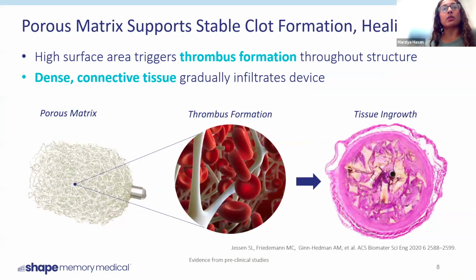And the way the embolization aspect of this device works is we have an extremely porous material where blood will make its way through the foam component, and it'll end up stagnating within the pores of the foam. That stagnation triggers the clotting cascade. And that's where we end up seeing the clot that forms to block the blood flow in the rest of the vasculature. And over time, what we have observed is that there is this dense connective tissue that eventually forms around the device. And I'll again go more into detail about this. Our foam component is biodegradable. So over time, we end up replacing our foam entirely with the body's native tissue. Thus, by treating the area effectively and without future treatments that are required.